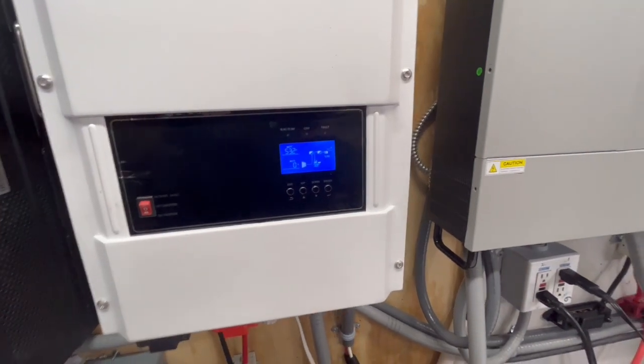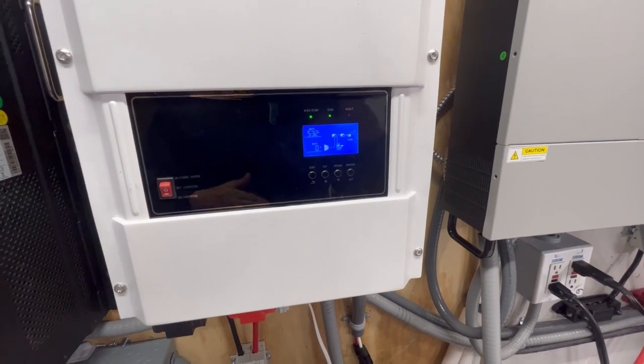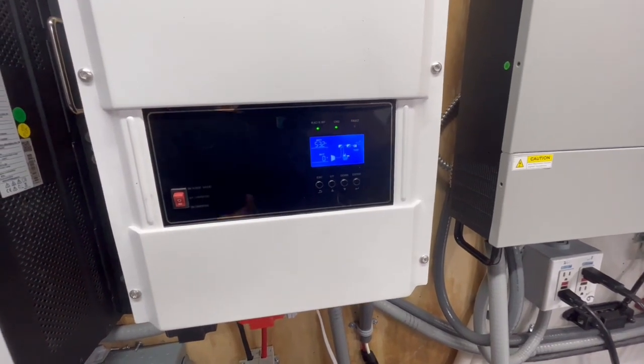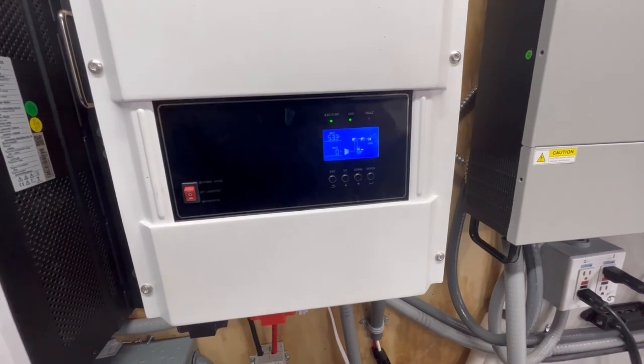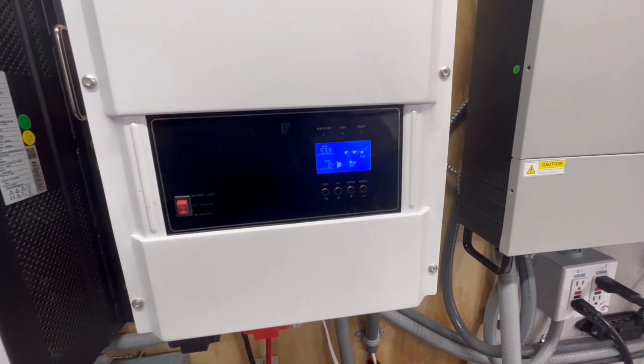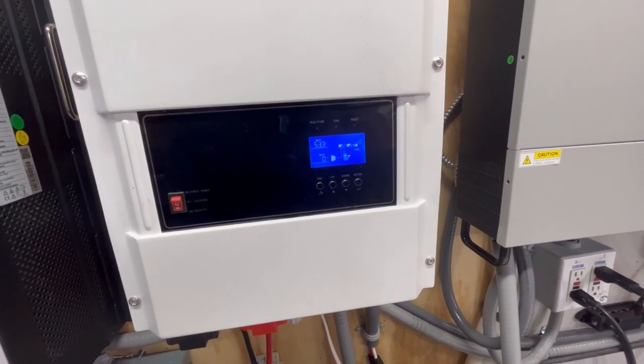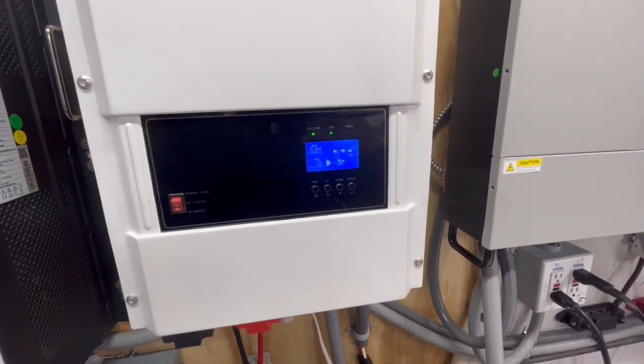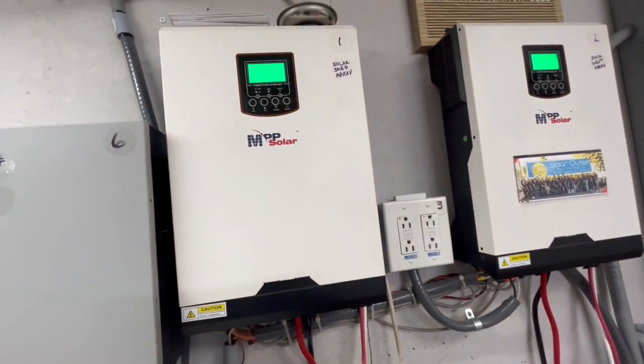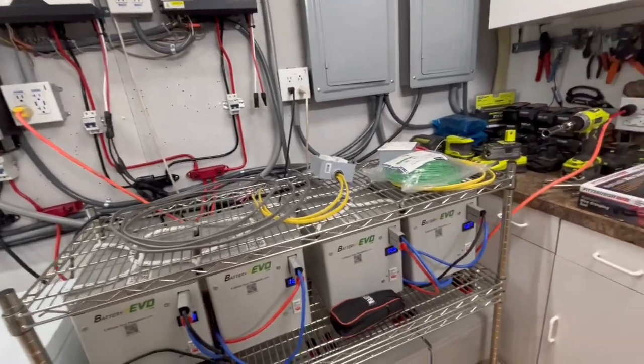What I usually do is start out 2 degrees warmer on the thermostat setting. If it's 65 degrees in the room, I'll set it at 67. When it gets to 67, I'll set it at 69. When it gets to 69, I'll set it at 71. That will extend the length of time we can run on the battery.